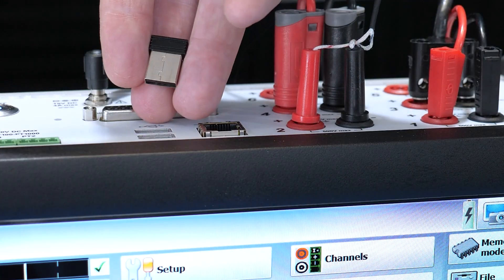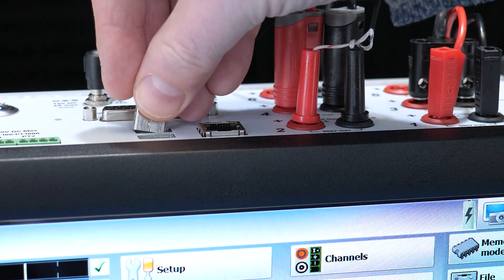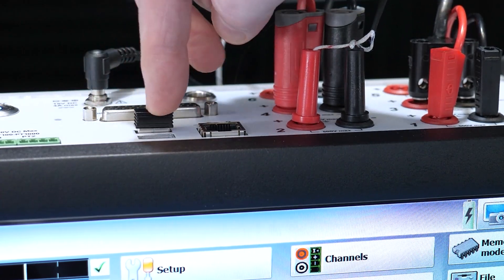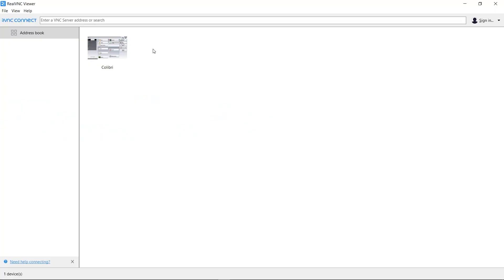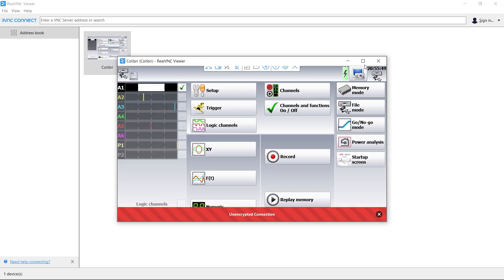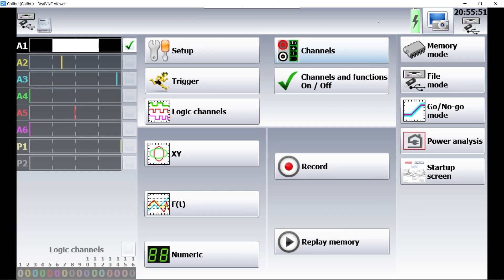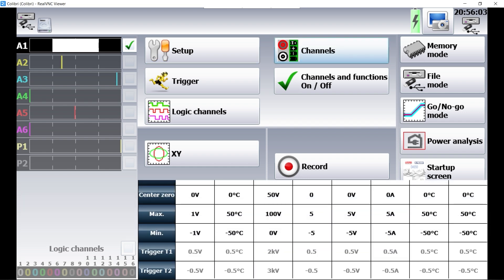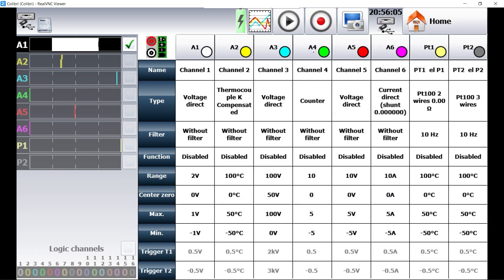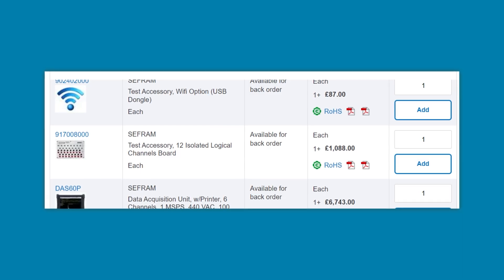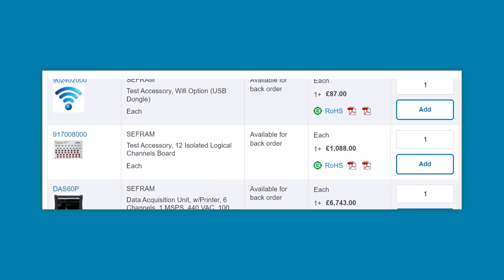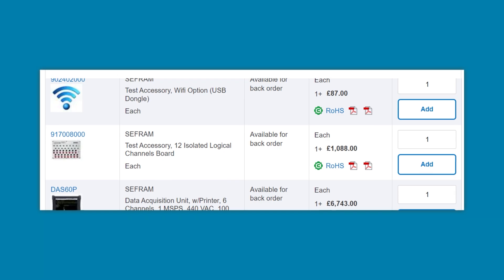But also, you can attach a USB WiFi dongle. Once connected by WiFi or ethernet, you can connect to the instrument using RealVNC. This connection lets you view the current state of the measurement or operate the user interface remotely. B&K does offer an official dongle for this unit. In my case, I found a generic adapter worked fine, although your experience may vary.